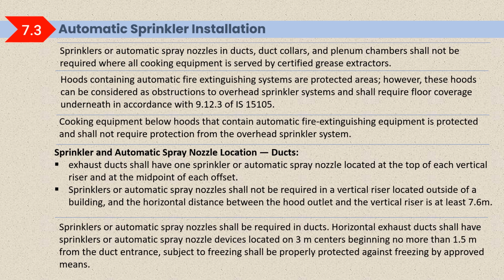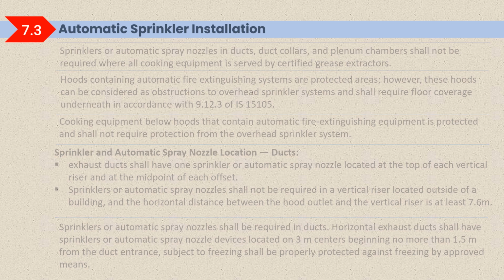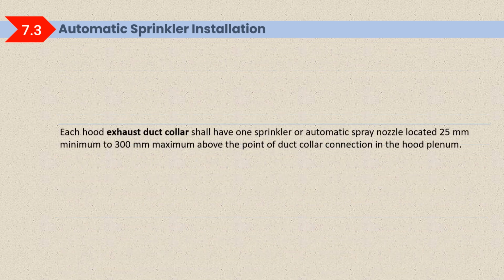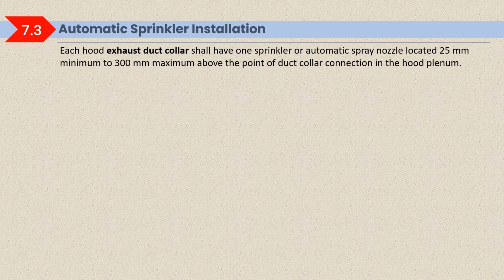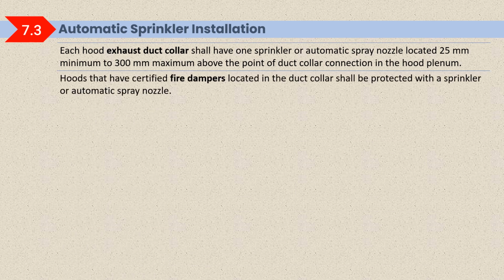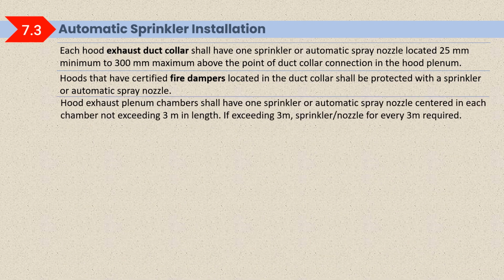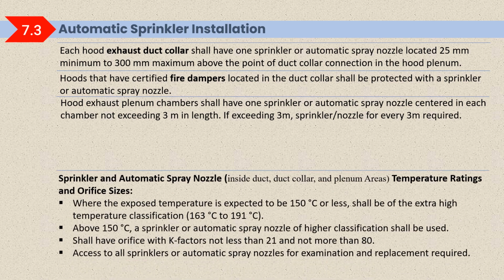Subject to freezing shall be properly protected against freezing by approved means. Each hood exhaust duct collar shall have one sprinkler or automatic spray nozzle located 25 mm minimum to 300 mm maximum above the point of duct collar connection in the hood plenum. Hoods that have a certified fire damper located in the duct collar shall be protected with a sprinkler or automatic spray nozzle. Hood exhaust plenum chambers shall have one sprinkler or automatic spray nozzle centered in each chamber not exceeding 3 meter in length. If exceeding 3 meter, sprinkler nozzle for every 3 meter required.